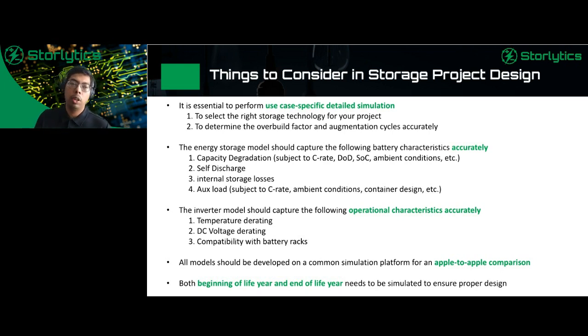Your energy storage model needs to capture factors like capacity degradation accurately. Several things can impact degradation, and those vary from technology to technology. For lithium, C rate, depth of discharge, and temperature play a very vital role. Some other technologies may not be as impacted by these factors, but you need an accurate model of degradation that reflects all these factors and their interplay.